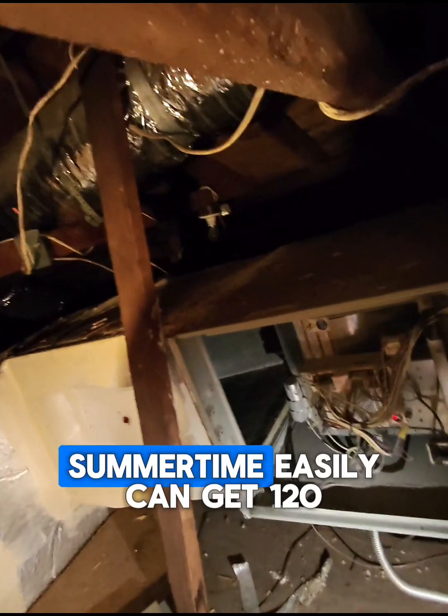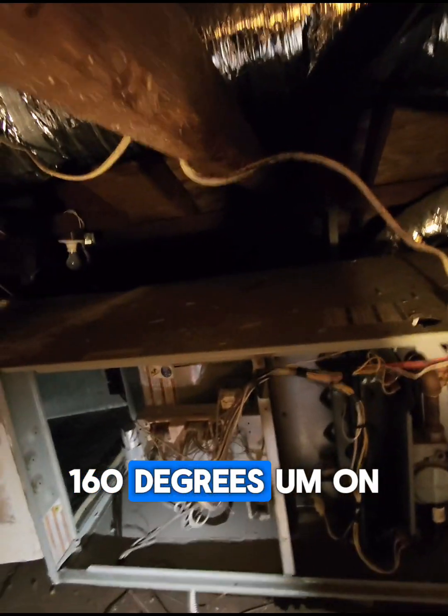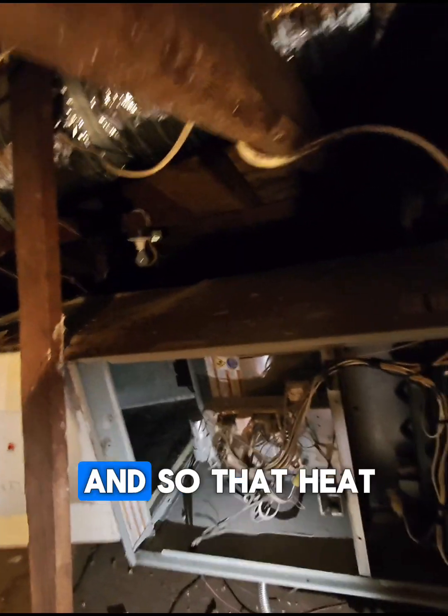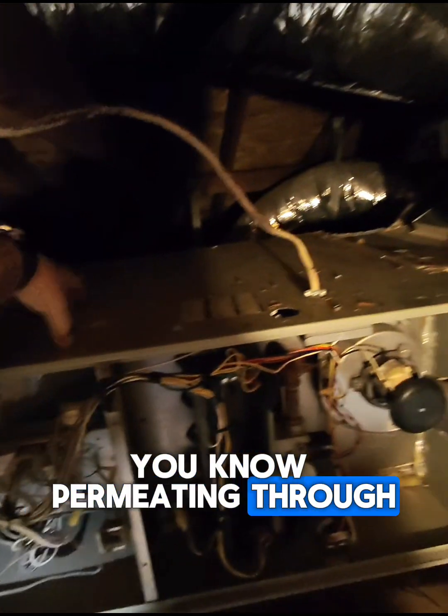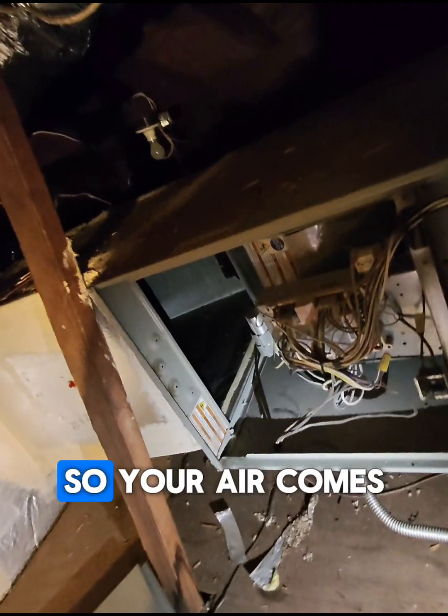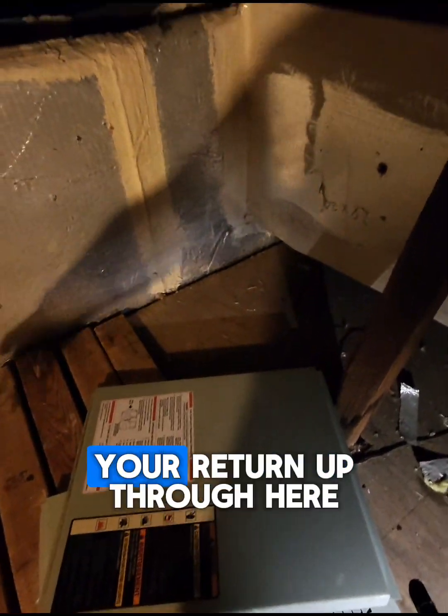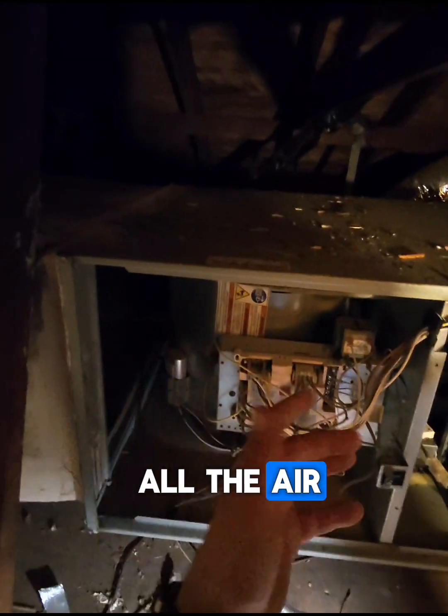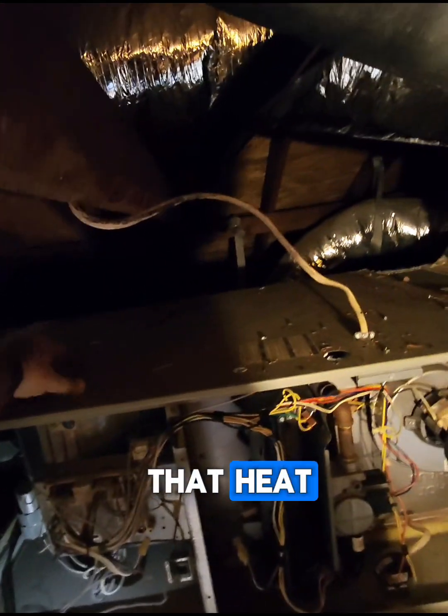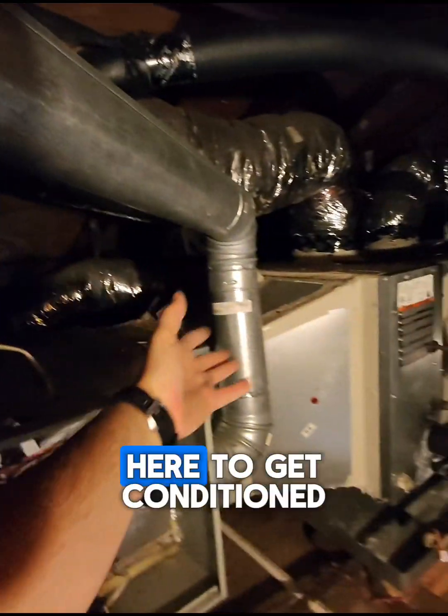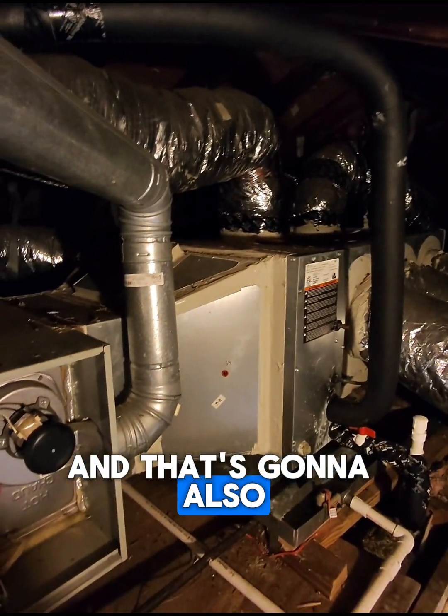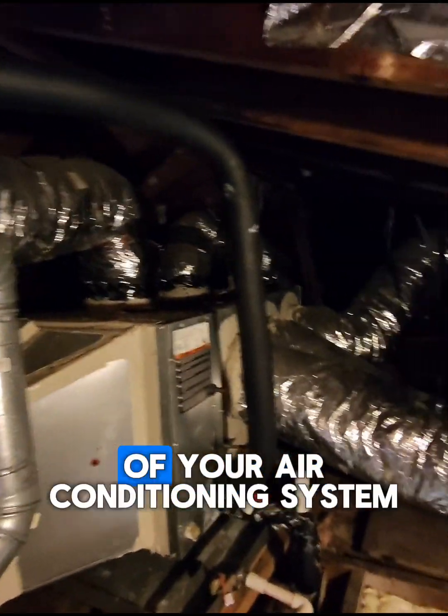This attic in the summertime easily can get 120, 140, 160 degrees on average in the summertime. And so that heat is just permeating through this equipment. So your air comes through your filter in your return, up through here, and then it goes through this. This is what moves all the air. So if it's having to go through this hot box before it gets to your system too, you could pick up a little bit of that heat, which is heating up your air before it goes over here to get conditioned. And that's going to also affect the performance and the overall efficiency of your air conditioning system.